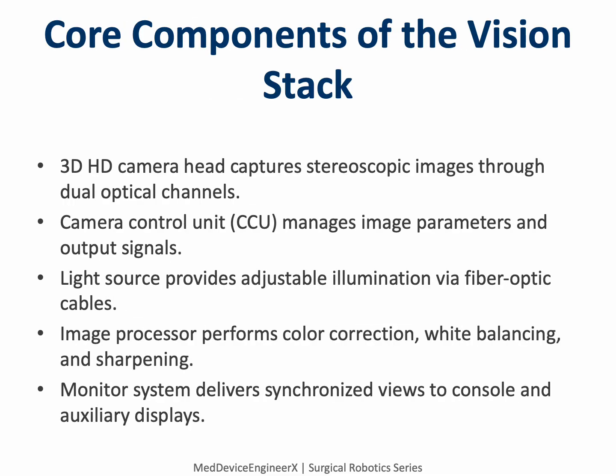At the heart of Hugo's imaging system is a series of components that each play a distinct role. The camera head captures light through twin optical paths, two miniature lenses that deliver the left and right perspectives needed for 3D vision. The camera control unit manages exposure, gain, and signal integrity, ensuring consistent brightness and color across varying tissue types. The light source, often LED based, provides cool, uniform illumination to avoid tissue heating.